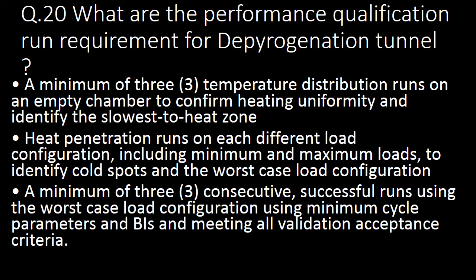Next important question: what are the performance qualification run requirements for depyrogenation tunnel? A minimum of three temperature distribution runs on an empty chamber to confirm heating uniformity and identify the slowest-to-heat zone. Second, heat penetration runs on each different load configuration including minimum and maximum loads to identify cold spots and worst-case load configuration. Third, a minimum of three consecutive successful runs using worst-case load configuration, minimum cycle parameters and biological indicators, meeting all validated acceptance criteria.